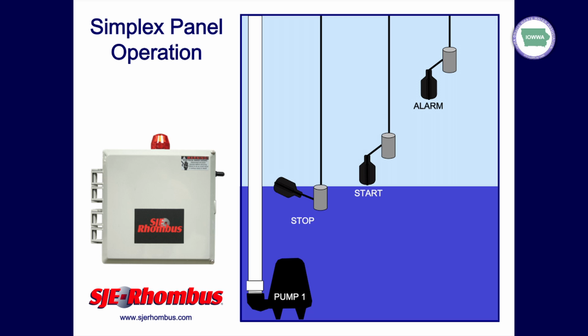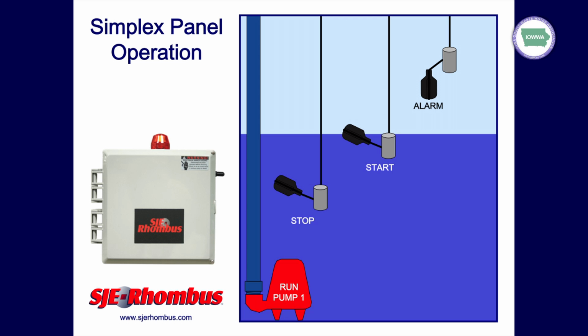And then we would recommend with your alarm float, you're going to have that high enough so you don't get nuisance alarms. You only get notified when you have a potentially catastrophic event. Typically, the high-level alarm going off is going to be a good indication that you've got either a pump that's bad or a float switch that's gone bad, something like that.